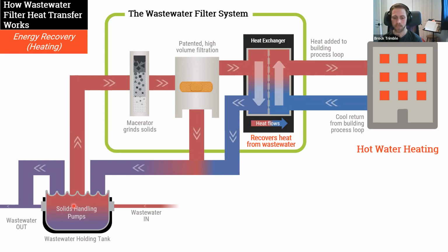Bob asks: Huber and others use mechanical wipers to clear buildup on their exchange plates—why is the SHARC approach superior to such mechanical wipers? There are a couple of things. SHARC systems see a much higher overall flow rate in our larger pieces than other competitive equipment. Also, the way we filter the wastewater and the way our piping and backflushing work through the heat exchanger has proven very effective—giving a smaller footprint, higher flow rates, better heat exchange overall, and completely sealed systems that keep the sanitary wastewater source isolated, clean, and odor-free.